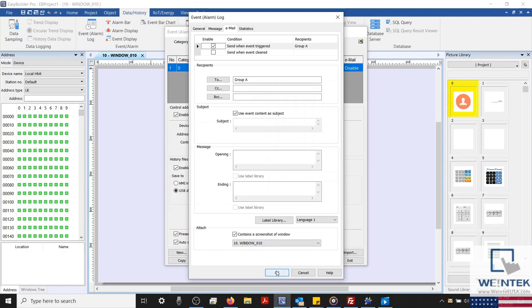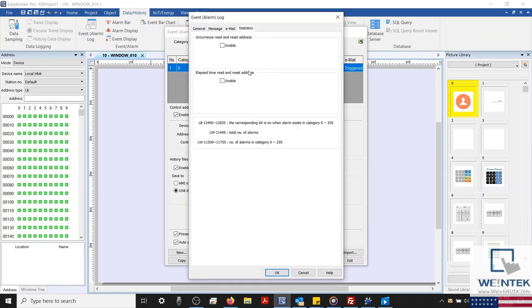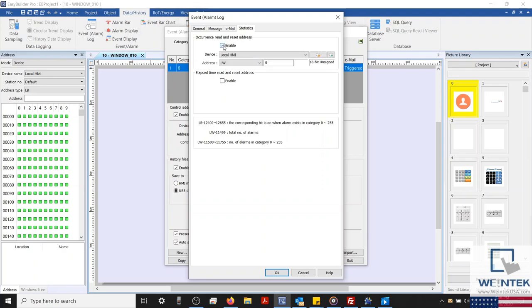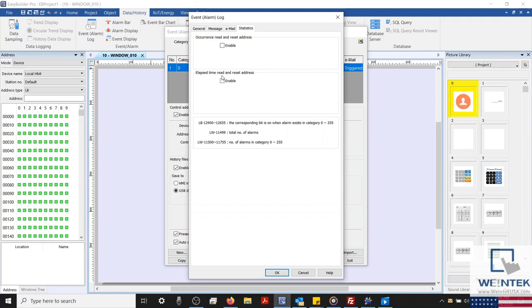Next, let's select the last tab and configure alarm statistics. There are several system registers that you can use to monitor alarm statistics within your project. If we enable the occurrence read and reset address, then the address configured will display how many times this alarm has been triggered since project boot. Our elapsed time read and reset address will monitor how long this alarm has been active within your project in seconds. And as stated, both of these addresses can be read and written to. This will allow you to reset the occurrence count or time stated.